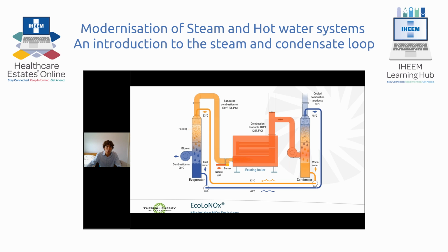The 63 degrees water is then passed through an evaporator, which is effectively operating in the opposite way of the fluace, to heat and humidify the incoming combustion air. And this is heated from 20 degrees C in the boiler plant to around 55 degrees C going into the boiler.